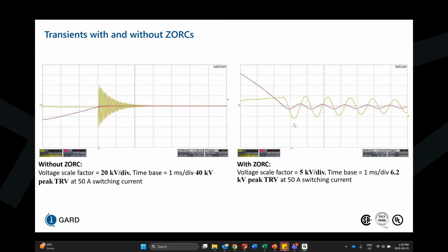So I'd imagine maybe after a few adjustments for transient overvoltages, you may have to replace one of the units, because you may be seeing bulges, or your pressure sensor on the unit, which is controlling the pressure inside of the enclosure, is alarming to you. Then that would be a cause for concern to address that you need to replace that ZORC.